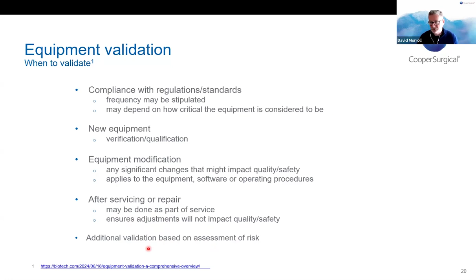The critical thing here is making sure that for any service or repair, where adjustments or new parts are involved, we make sure that they won't impact what we do. They won't impact quality and safety. And then, of course, you may well be aware that ISO accreditation has all moved now to risk-based models. So if you do risk assessments, and you feel there's an increased risk, you would automatically trigger an additional validation process.